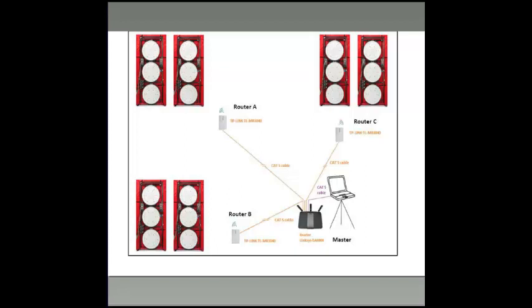One of the ways, a lot of times with commercial testing, you want to try to minimize the cabling. If I've got a monster building and I've got 2,000 feet from my master control station to my banks of fans, if I've got to run 6 individual Cat5 cables, that's a lot of extra work, and I can simplify that by using a smaller router.